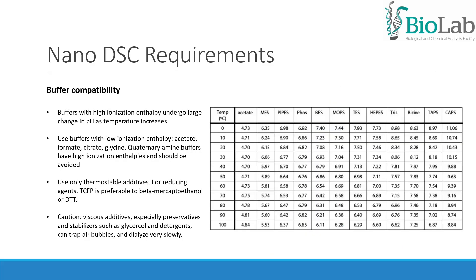Regarding buffer compatibility, buffers with high ionization enthalpy undergo large changes in pH as temperature increases. You should use buffers with low ionization enthalpy such as acetate, formate, citrate or glycine. Quaternary amine buffers have high ionization enthalpies and should also be avoided. You should use only thermostable additives. For reducing agents, TCEP is preferable to beta-mercaptoethanol or DTT. Have caution with viscous additives, especially preservatives and stabilizers such as glycerol and detergents, because they can trap air bubbles and dialyze very slowly and interfere with the DSC scan.